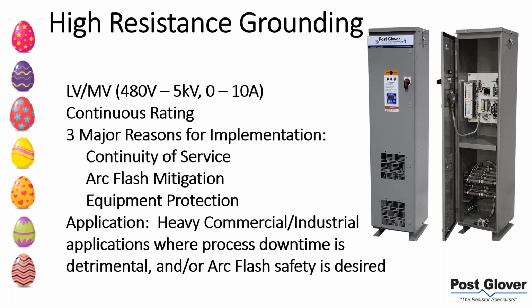There was a paper that was done a few years ago. I'm sorry, I cannot quote it for you, but essentially the bottom line of it was about 95–97% of your arc flash potential is mitigated. Just to make sure I'm clear, that doesn't actually mean anything in terms of arc flash gear or category, because your worst case is still there. But in terms of the number of events or the possibility of events, it's drastically reduced. And of course, if you're operating at very low current, there's the equipment protection it affords you.